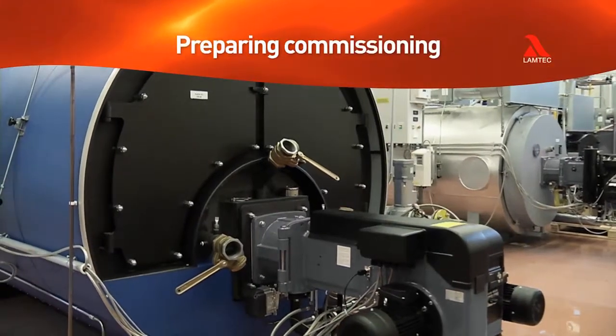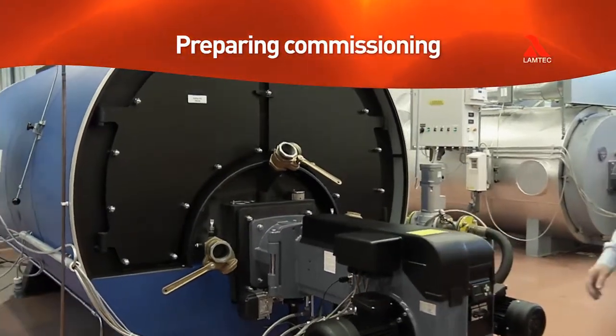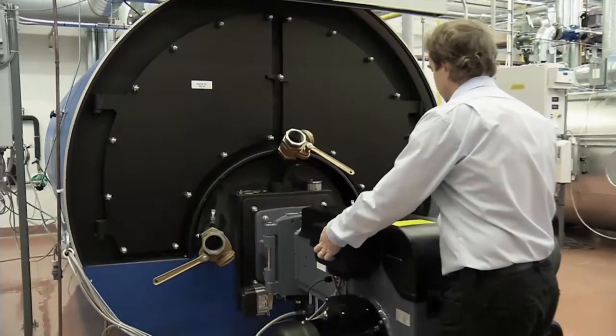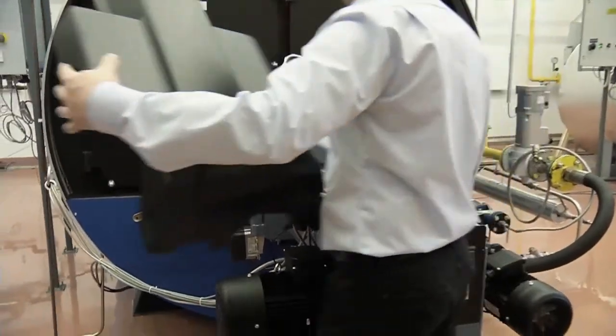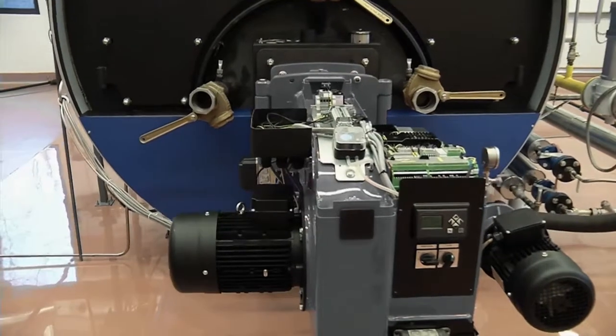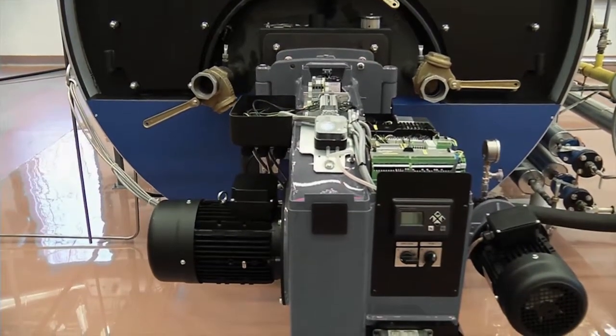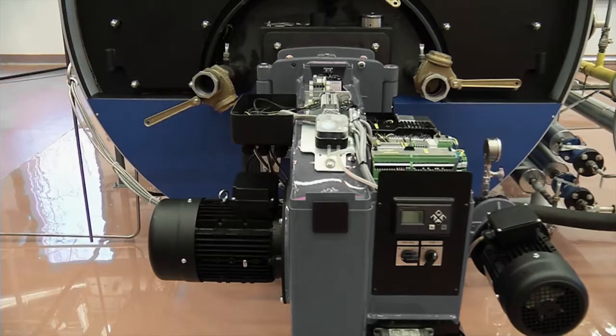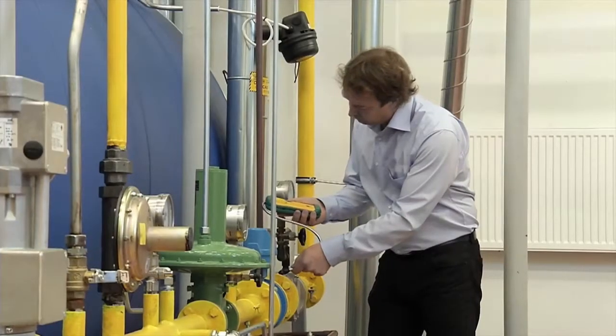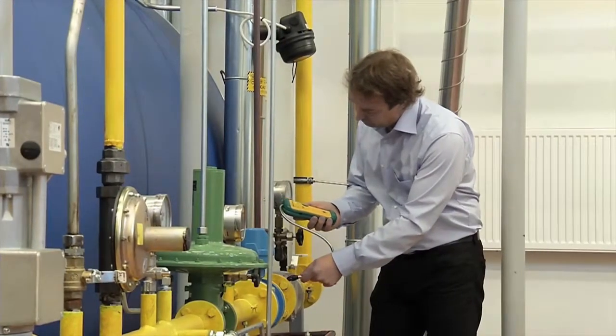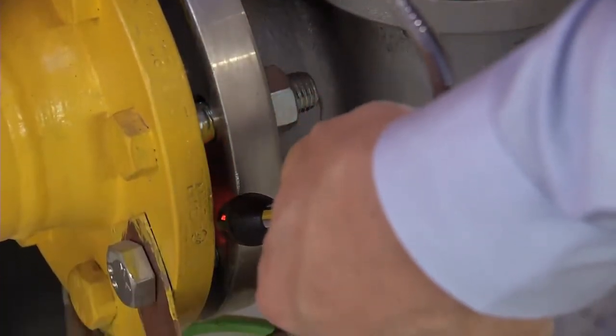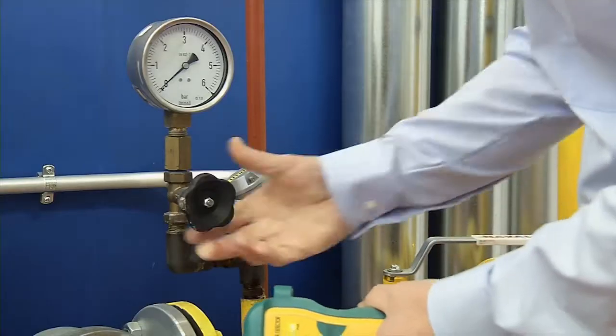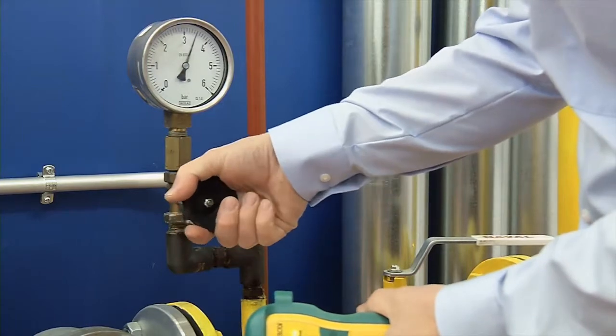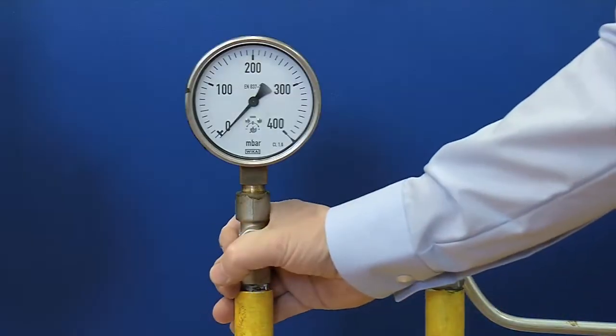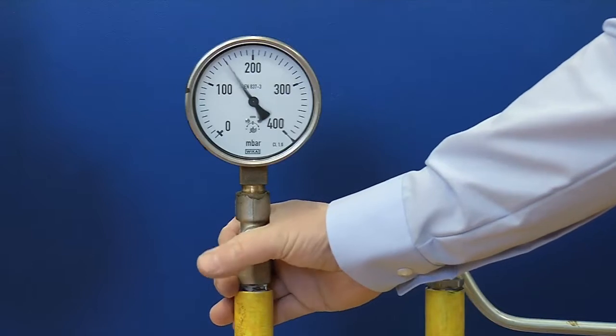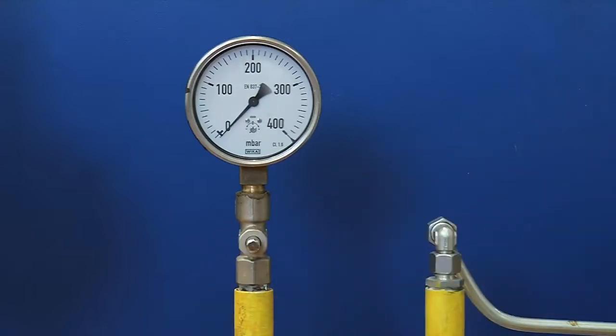Before the first startup, always check the fuel lines, electrical equipment, and hoses along with their connections. Naturally, there should be fuel available and sufficient amount of water in the heating system. Make sure that piping is installed correctly and its joints are tight and have no leaks. You should check that the piping valves are opened and then test the gas piping carefully for leaks. Using the pressure gauge, make sure that the fuel pressure is adequate.